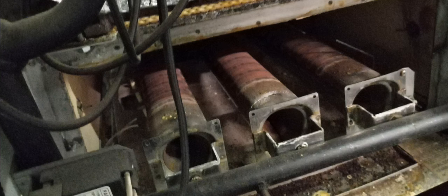So what was done, the ignition board on the left was changed over, the aqua board was also changed over, and the burners were taken out of the decommissioned unit, cleaned up, put over, combustion tested and so on, burner adjusted and so on, gas valve adjusted accordingly, and made sure it was safe, checks carried out, and then the unit stopped cutting out. So it looked as though it was down to the burners or possibly the ignition board.